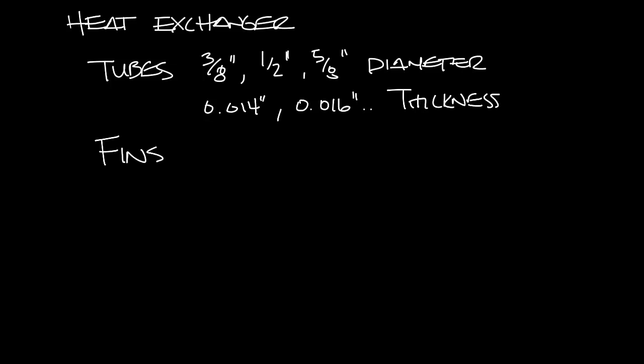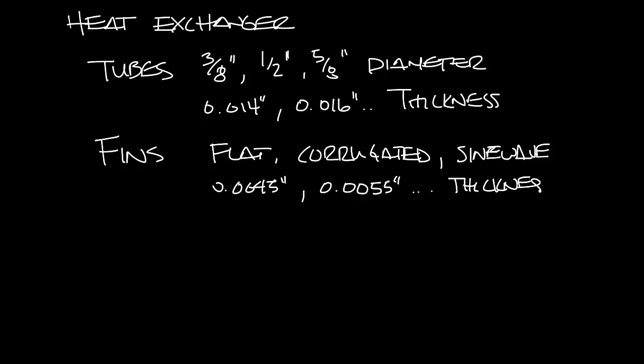The fins can be different styles. They can be flat, corrugated, a sine wave, and some other shapes. And they can have different thicknesses as well so they could be 0.0045 inches, 0.0050 inches, and so on. And then you can also have different number of fins per inch so you could have like 10 or 12 fins per inch.